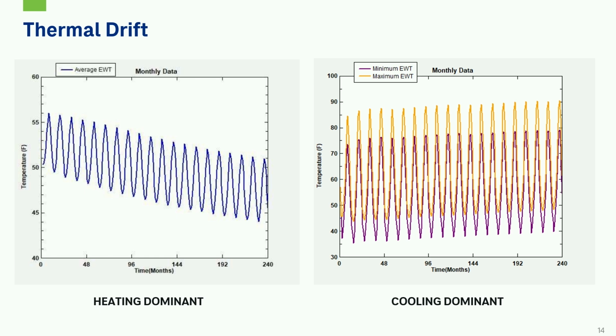We can see what the entering water temperatures are, and we have our design points. So typically it could be anywhere from like 40 to 80 degrees or 30 to 90 degrees. And as long as those lines are within those two temperatures that we're looking for, like you can see on the right that they just make it to 90 degrees at the 20-year mark. But when we're designing, we want to make sure that we have enough boreholes and that it'll last for those 20 years. But if we're seeing significant thermal drift, if we have too few boreholes or something like that, and those entering water temperatures exceed those design threshold points, then we can say, okay, it won't be able to serve us past X amount of years. Oh boy, here we go. Question for you back there?